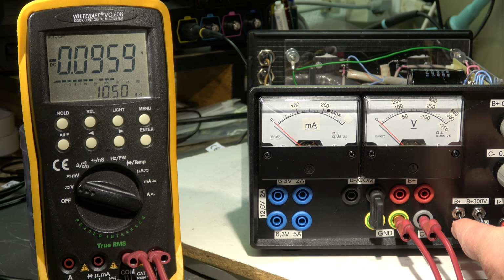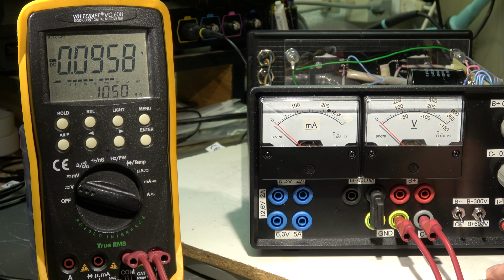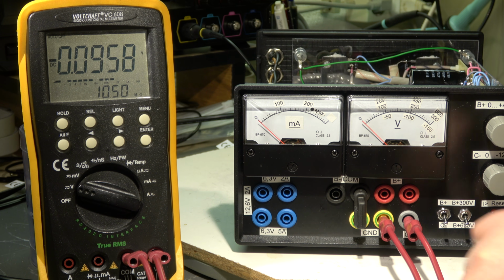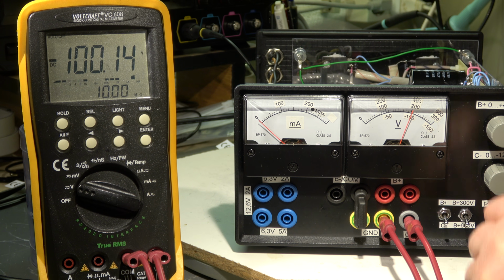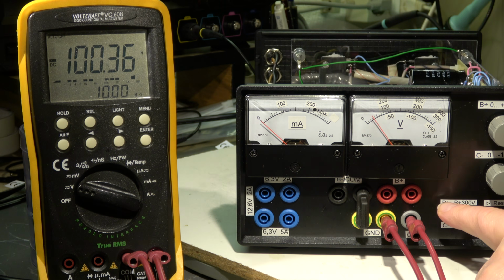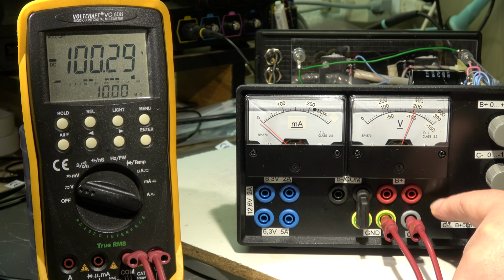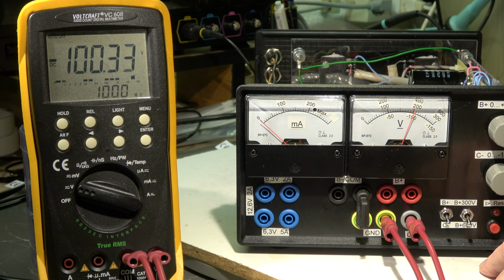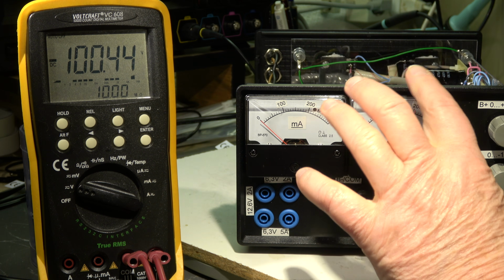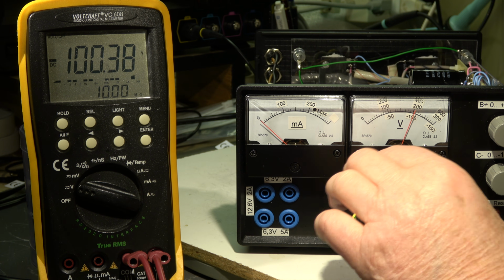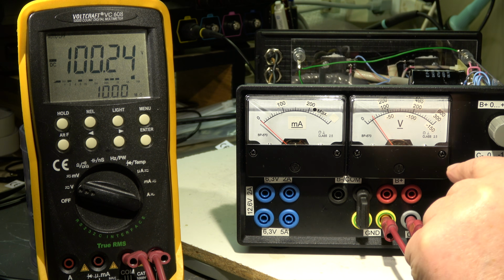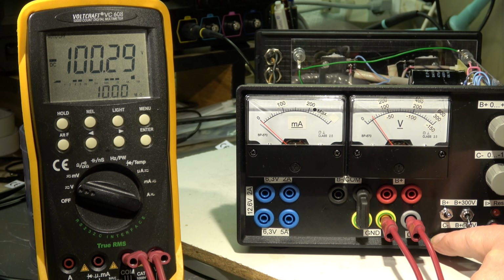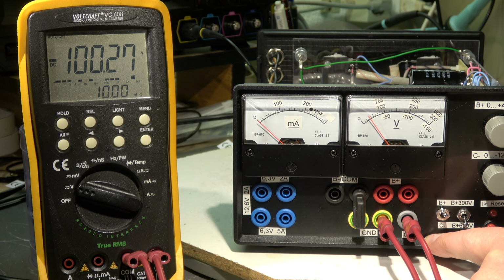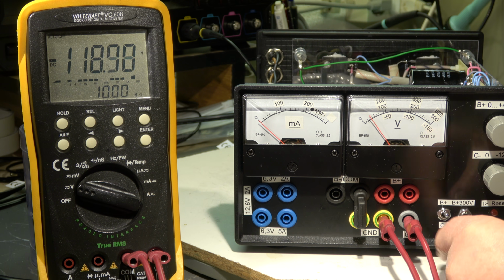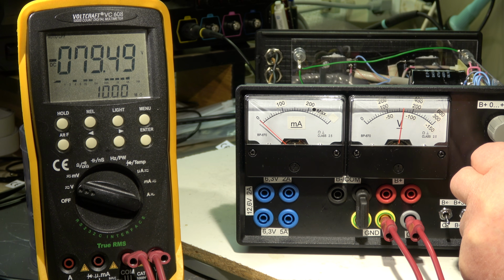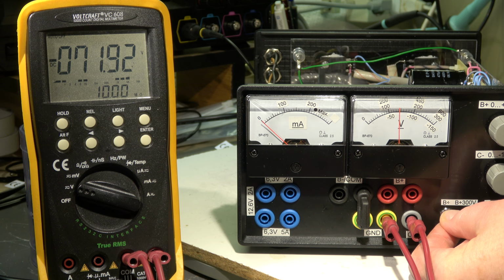So when the instrument is switched from C minus measurement to B plus, then there has to be an artificial load to compensate for the change of the impedance. And we can see when I have, for example, minus 100, and when I switch the instrument to B plus, this voltage does not change. This is done by a special arrangement of the switch, which replaces the instrument by a short circuit to ground. We have a series impedance of 150 kilo ohms. The instrument itself has only 230 ohms, so we have 150k, and there's the option when I switch to B plus, and the 150k, the series impedance, is connected to ground. So the C minus source sees again 150k ohm to ground. So it is a constant load, and the output voltage, sorry, I'm on B plus here. The output voltage does not vary when switching between B plus and C minus.